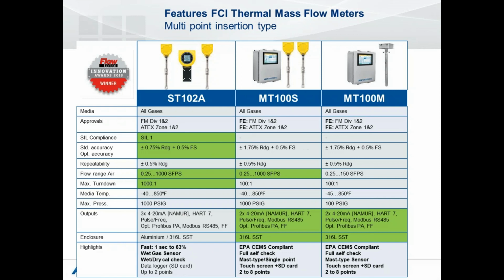So with that, the crossover between the ST102 and the MT100 as far as overall accuracy goes comes into play around 40 to 48 inches. At that point, the base accuracy of the 102A is overcome, because we're only 2 points in a large system. Flow range, 1/4 foot per second for the single point sensors, well, actually across the whole range. But the S's, in the 102A, you're able to get up to 1,000 feet per second. Some turndown capabilities. And then feature-wise, again, that CEMS compliance is in the 100s. For the 102A, we still have the ability to do the wet gas sensor as a special. And it's got that data logging capability as well.